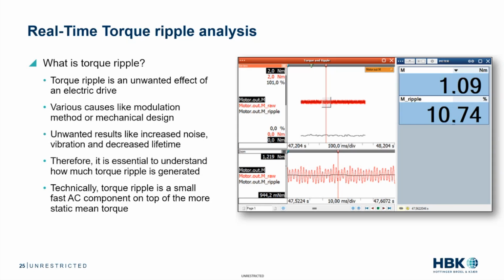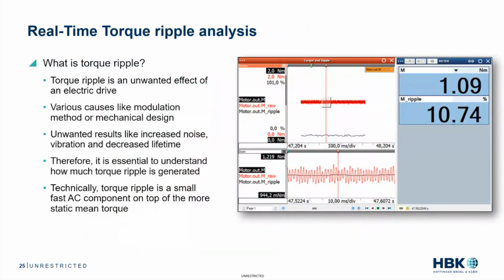And here's a nice little example screen that has been set up where you have torque ripple, which is a small, fast AC component on top of the more static mean torque. So here we have two graphs. The square you see in the top is actually magnified on the bottom graph, where the black line is the average static torque, but the red signal is the torque ripple. And there's an automatic measurement that gives you a percentage of the torque ripple based on the total torque that's being measured. In this case, we see it's 10.74% of the 1 Newton meter torque. So this is very valuable information, so you can try to identify means and make measurements and improve your actual motor and your inverter to try and reduce the noise, the vibration, and increase the lifetime of your system.